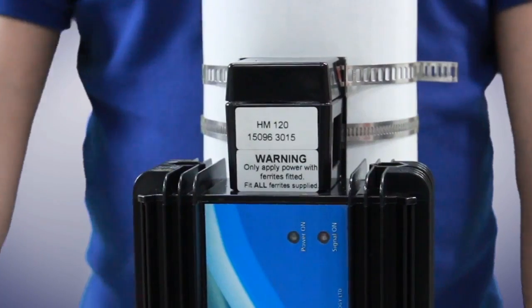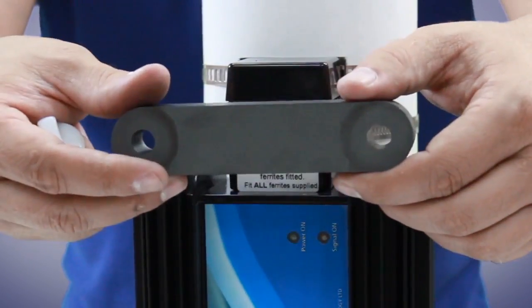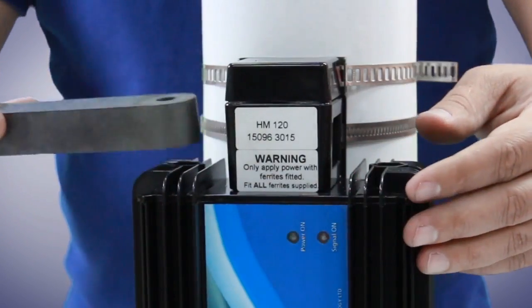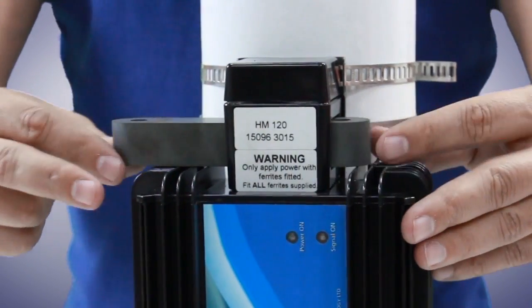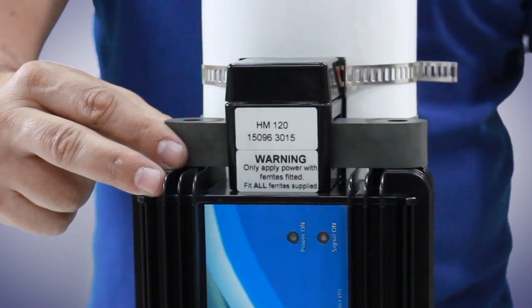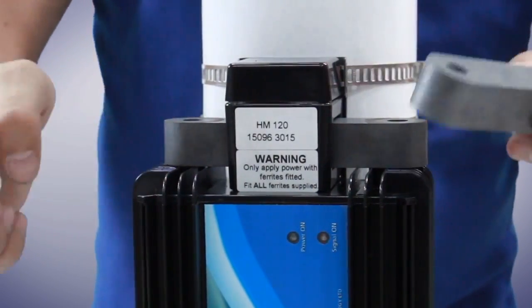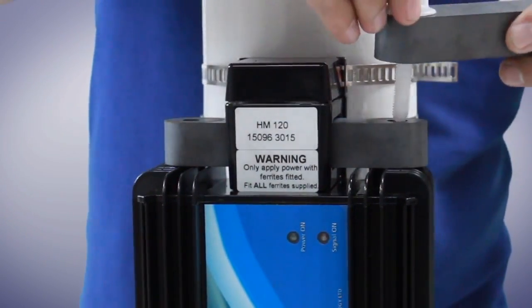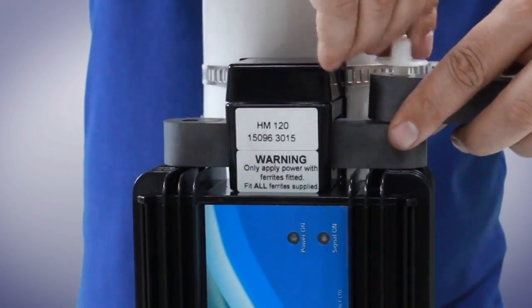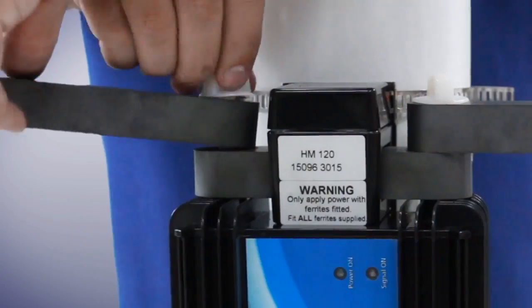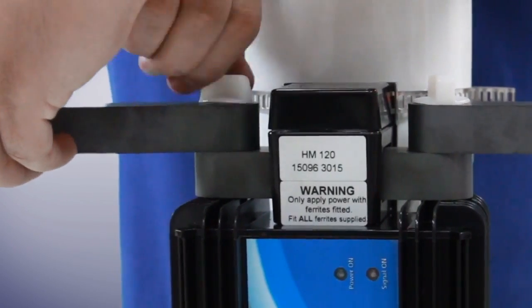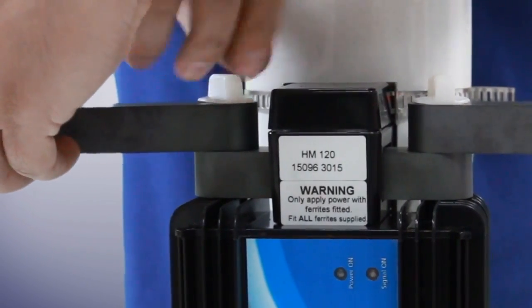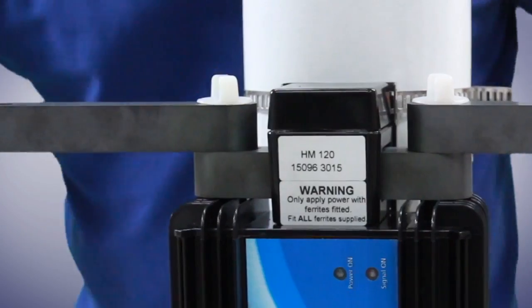The unit is supplied with at least one long ferrite. Take a long ferrite and insert it through the holding cage until the holes line up with the hexagon nuts. Take a second ferrite and insert a thumb screw through the holes of both ferrites. Loosely screw into the hexagon nut. Repeat on the other side. There is no need to fasten the screws tightly at this point.